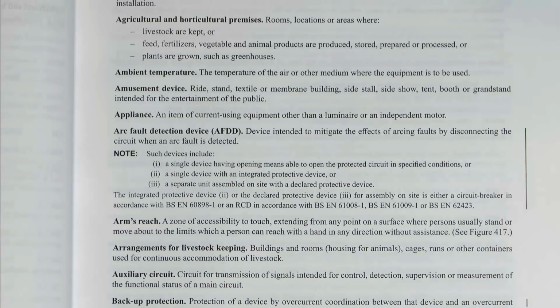So there's various ways these things can be done. Obviously it's important to distinguish between them, because if you need overcurrent protection and arc fault detection, you don't want to just stick in an arc fault detection device, which would leave the circuit wide open to overloads or overcurrent.